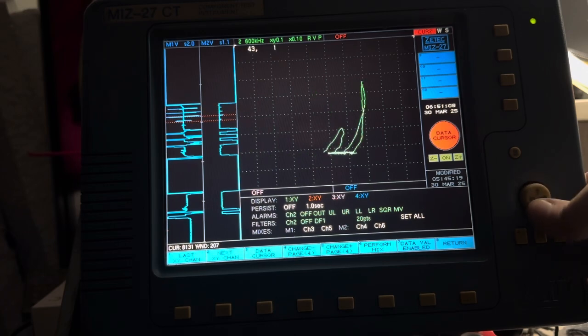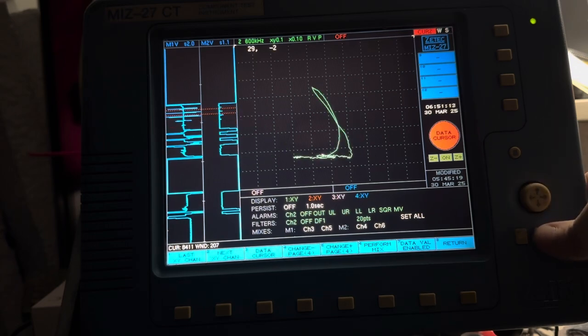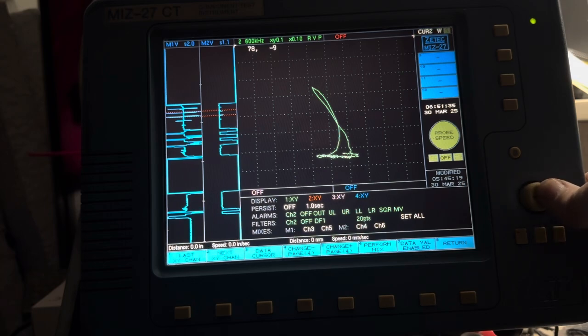Now I can guarantee it, if you walk into a room full of data evaluators and they're analyzing data from, for example, a heat exchanger inspection where they're using inside bobbin probes to examine the tubes, you are not going to hear them talking about impedance and inductive reactance and resistance. If you are, I'd be very surprised, because that would be rare. Because what you're really watching for when you evaluate data are changes to signal phase and amplitude.